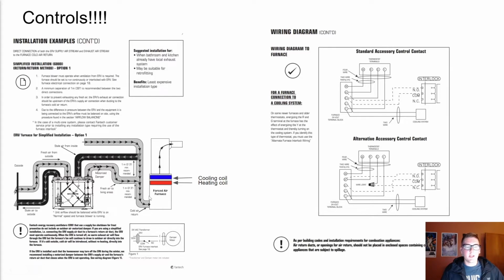When both run together, the outdoor air gets conditioned by your return air, and then before it gets distributed within your house, you have either your heating coil, if you're in heating, or cooling coil, to further condition that air and make sure, in cooling, your discharge air is going to be close to 55F, or in heating, you're going to be at 100 or 110F as it goes out. And so that's going to be working how you want.